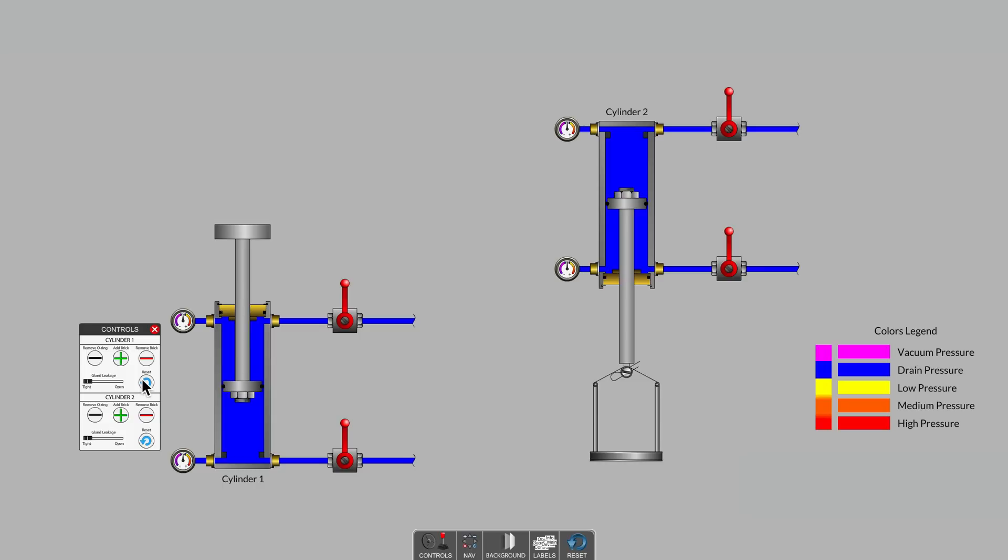In this video, we will look at issues pertaining only to cylinders that drift in the inward or retract direction. In another video, we will look at cylinders that drift outward toward the extend direction. To make it clear that we are only examining the cylinder and no other parts of the hydraulic system, we have closed the shut-off valves to both the blind end and the rod end cylinder ports.